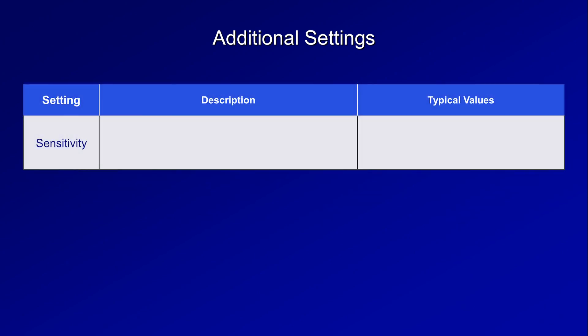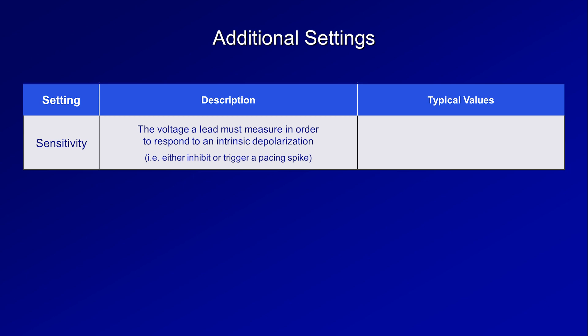In addition to timing cycle settings, there are three additional important settings. First is sensitivity — the voltage a lead must measure in order to respond to an intrinsic depolarization, either inhibiting or triggering a pacing spike. The lower the sensitivity setting, the more sensitive the pacemaker, and vice versa. Sensitivity should have a safety margin of about 2, so if an atrial depolarization has an amplitude of 1.0 mV, the sensitivity should be no higher than 0.5 mV. Typical default settings are 0.5 mV for an atrial lead and 2 mV for a ventricular lead.